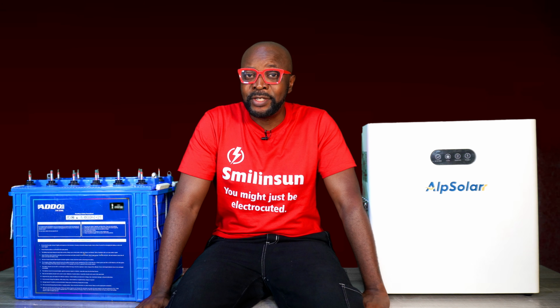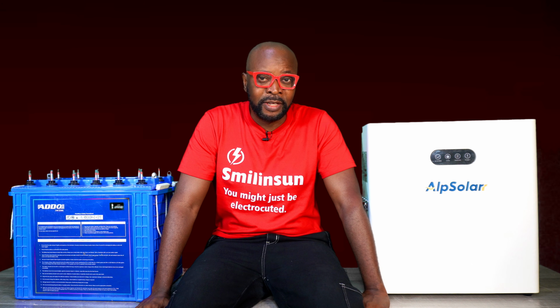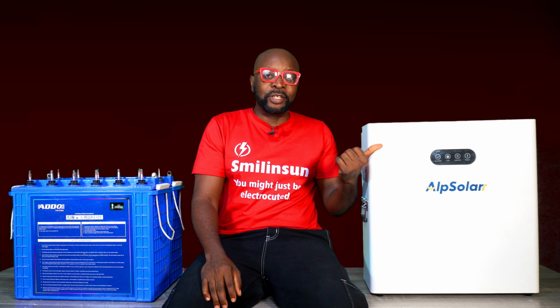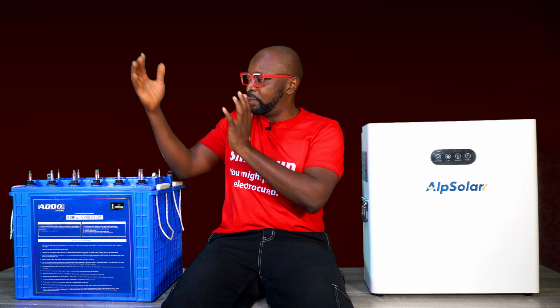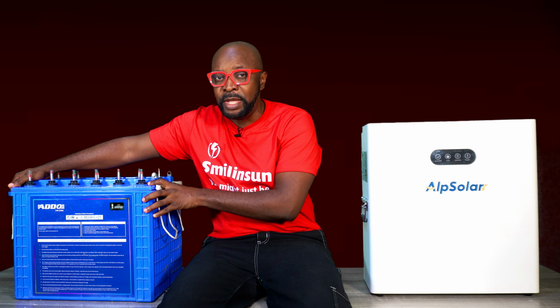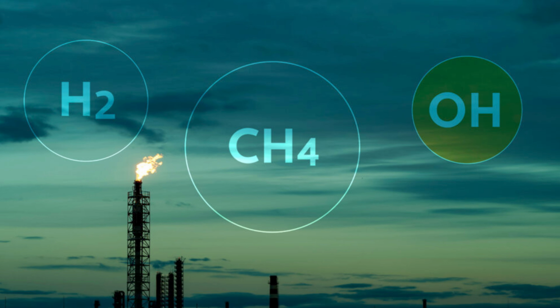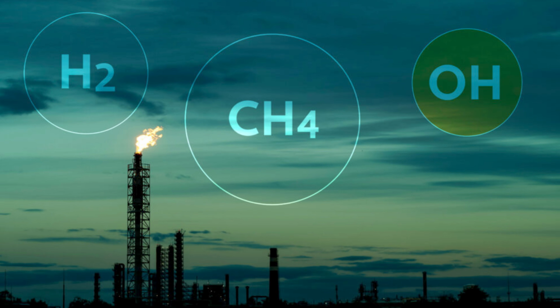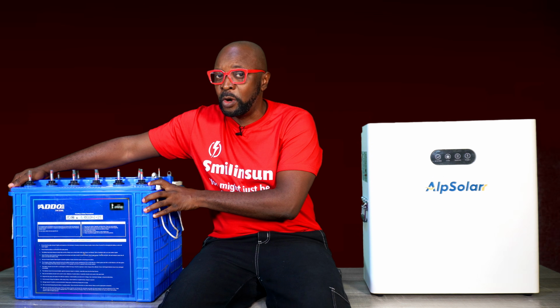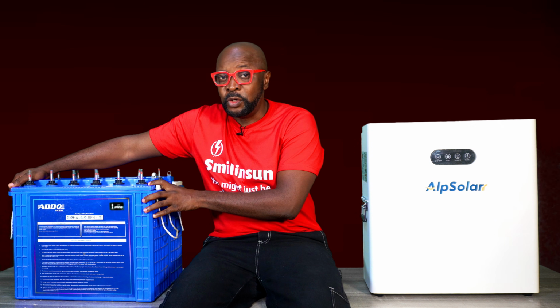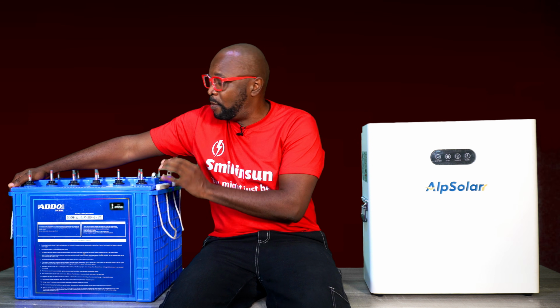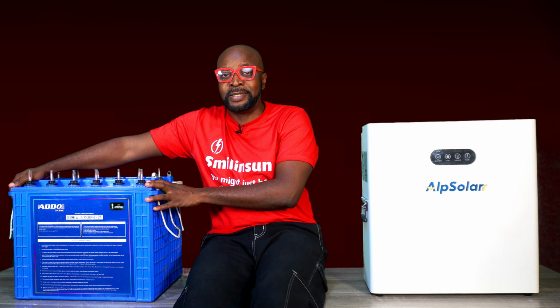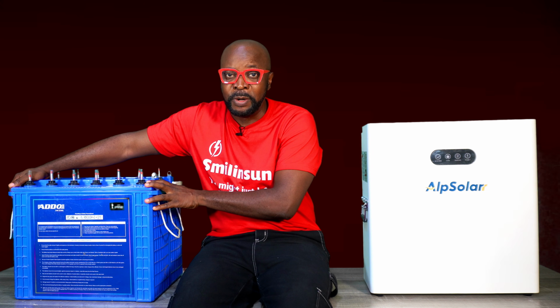So which of these two batteries is considered to be environmentally friendly? That will be the lithium battery. But let's look at the tubular battery first. The tubular battery, while it's charging, emits hydrogen gas, which is deemed to be very harmful to your health. And it even becomes worse when you're doing equalization, because you need to do equalization periodically on these batteries to be able to balance the cells and get them to operate very smoothly.